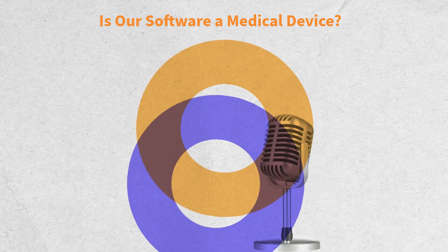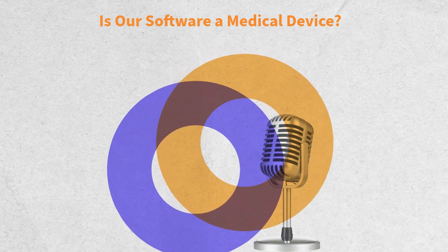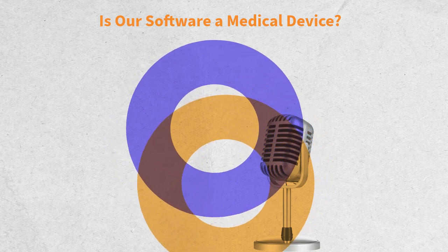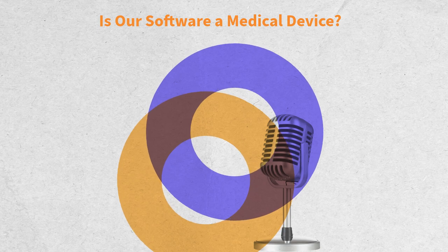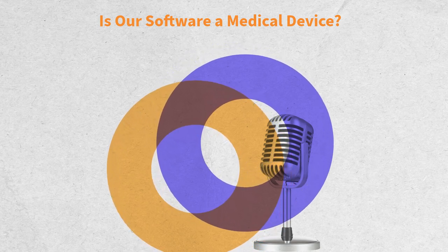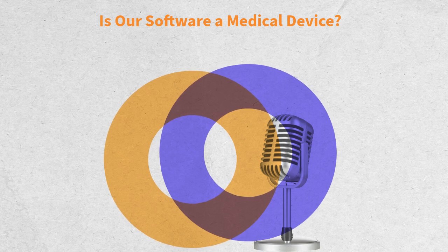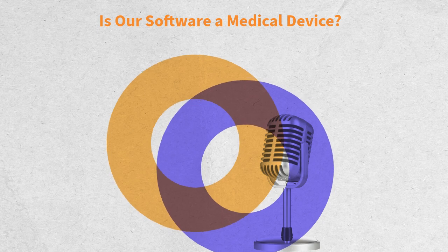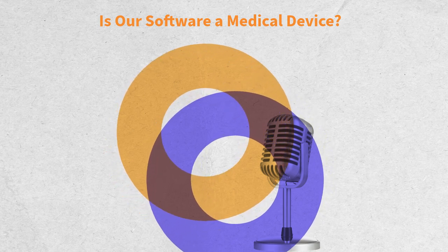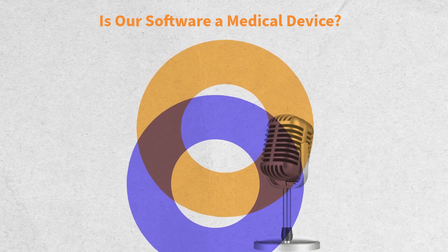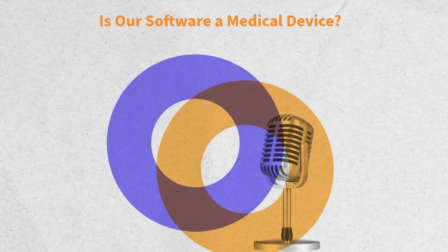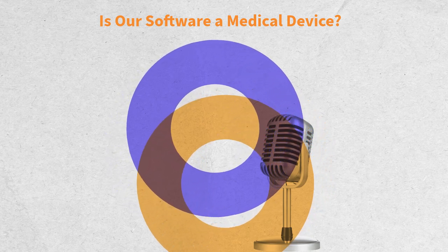Is a software supporting clinical decision a medical device? Yes. The so-called CDSS, Clinical Decision Support Systems, clearly fall into the category of medical devices if they directly affect the diagnostic or therapeutic pathway. Also in this case, the logic of Rule 11 applies. If the decision affecting the patient's health may depend on the output, then you are in the framework of the MDR.